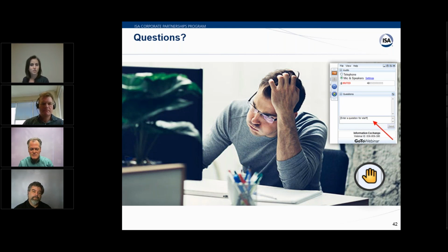Thank you, Ian. So assuming that the process under observation is in a steady state, can we still use only acids and bases to calibrate the electrode? And how will the sensitivity and accuracy be compromised in the process? Well, as we said, it's more about repeatability, right? I've done it, and we've all done it. We live in the plant, and we have to make the big assumptions. Repeatability is key, and if we're able to consistently get a reference between that acid or base that we're using and what we're measuring with our sensors, then that'll work, right?